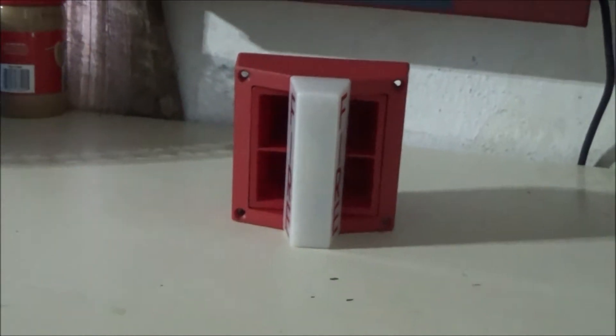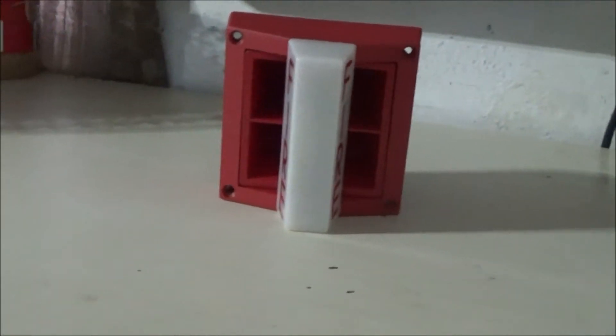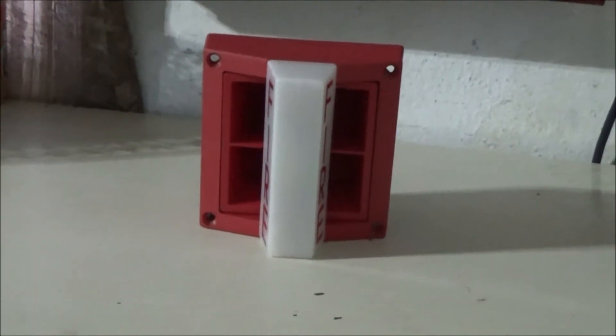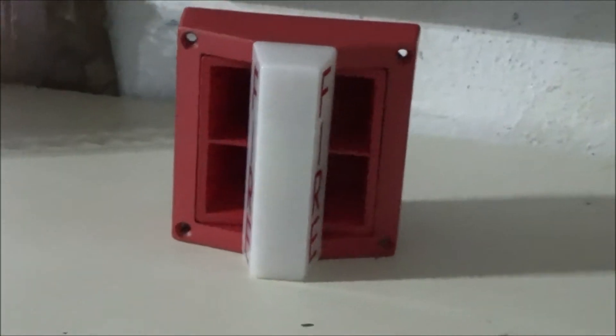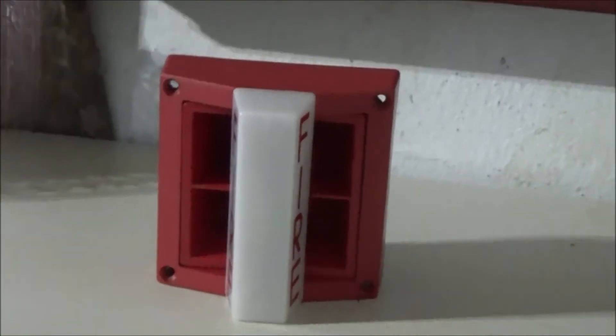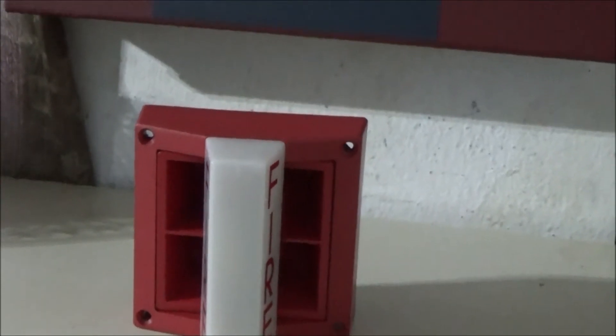What I like about this device is it's very early and old, and this is probably one of the first multi-tone devices out there, along with Wheelock. But the problem is that you will have to break its tab in order to change its tone. That's right — you have to break its tab.